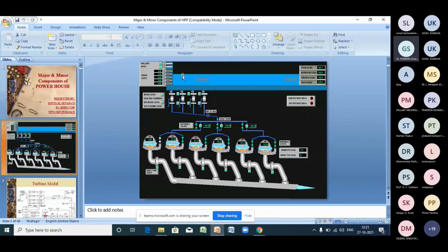So they have desilting chambers. We have to remove the silt available during the travel of water from the intake towards the turbine. The main reason is very simple. We just widen the area of the flow. That means initially, in the cross-sectional area where the water is flowing from the intake, in certain patches we increase the cross-sectional area or the volume, so that the velocity of the water traveling from the intake to the turbine will be a bit slower.